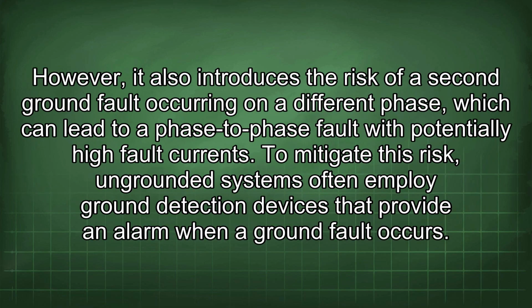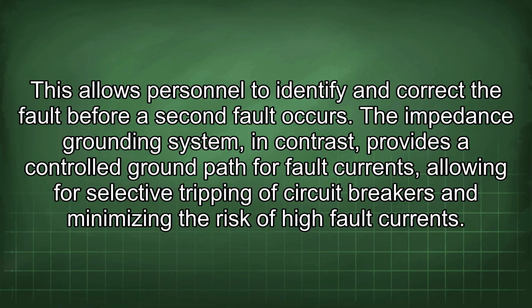However, it also introduces the risk of a second ground fault occurring on a different phase, which can lead to a phase-to-phase fault with potentially high fault currents. To mitigate this risk, ungrounded systems often employ ground detection devices that provide an alarm when a ground fault occurs. This allows personnel to identify and correct the fault before a second fault occurs. The impedance grounding system, in contrast, provides a controlled ground path for fault currents, allowing for selective tripping of circuit breakers and minimizing the risk of high fault currents.